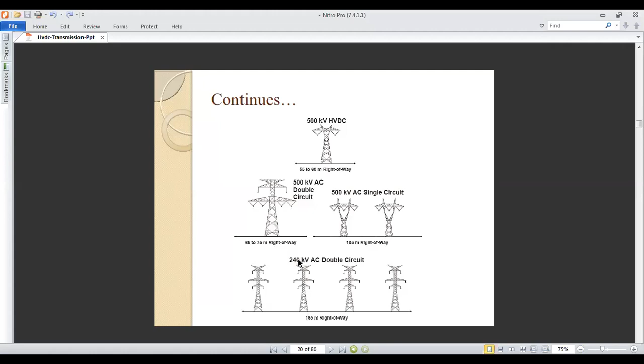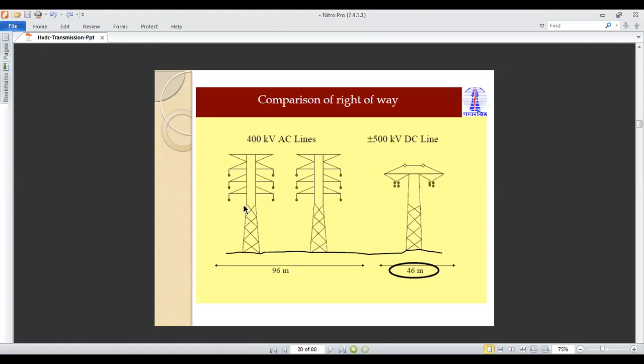So this implies that for a given power level, a DC line requires less right of way, simpler and cheaper towers, and reduced conductor and insulator loss. The power losses are also reduced with DC, as only 2 conductors are used. As you can see, in the case of DC the power loss is very low because only 2 conductors are used, but here we are using 4 conductors: 1, 2, 3, 4.